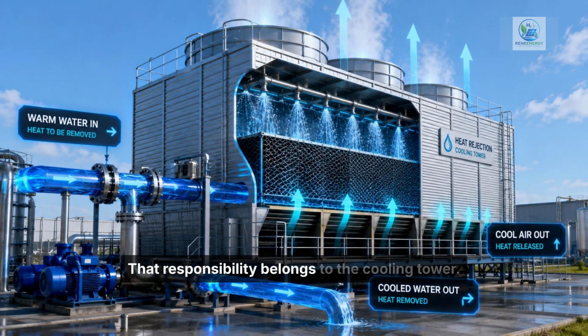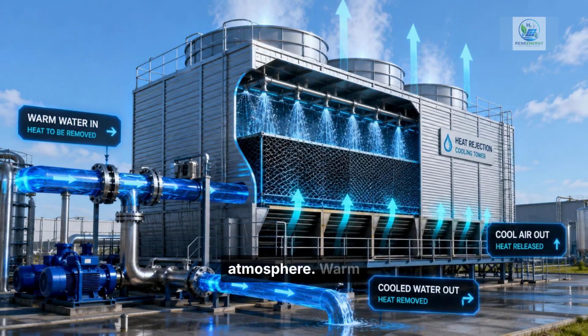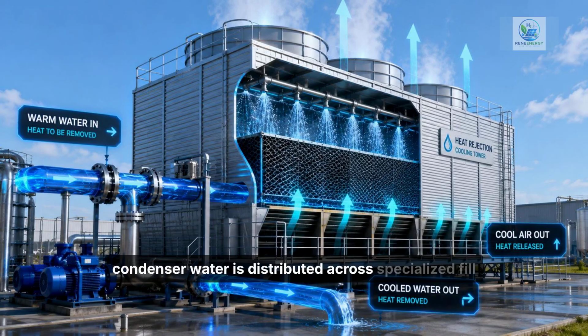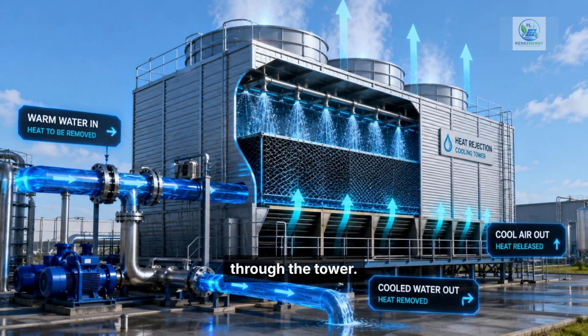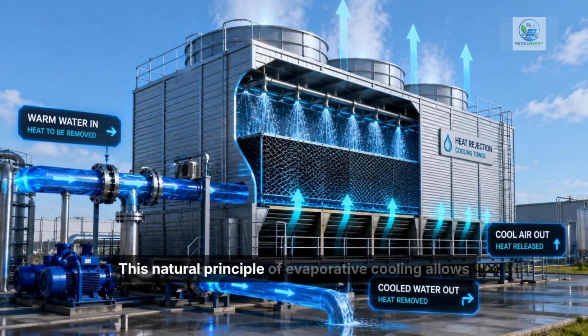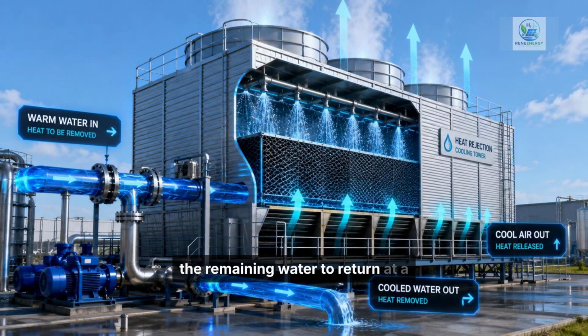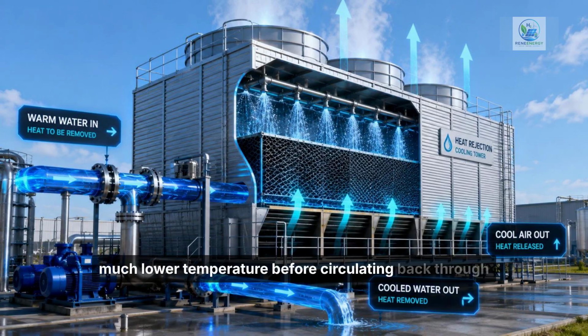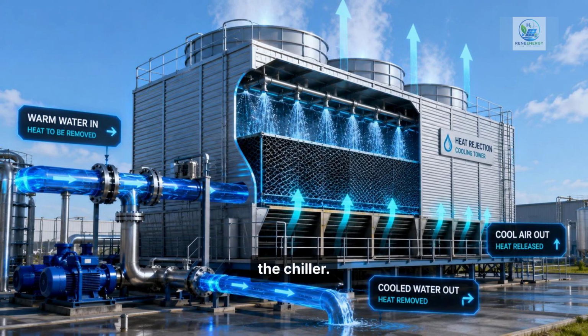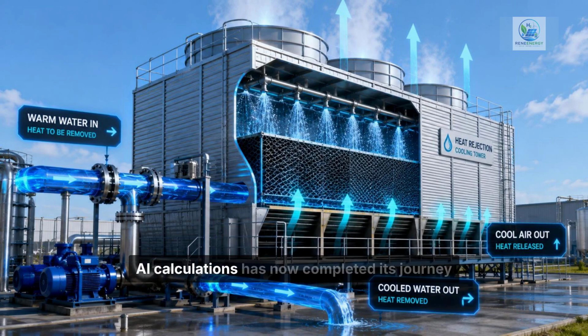Although the chiller cools the water, the heat itself still has to go somewhere. That responsibility belongs to the cooling tower. Located outside the building, these towering structures release the captured thermal energy into the atmosphere. Warm condenser water is distributed across specialized fill material, while large fans pull air upward through the tower. A small portion of the water evaporates, carrying away significant amounts of heat in the process. This natural principle of evaporative cooling allows the remaining water to return at a much lower temperature before circulating back through the chiller.